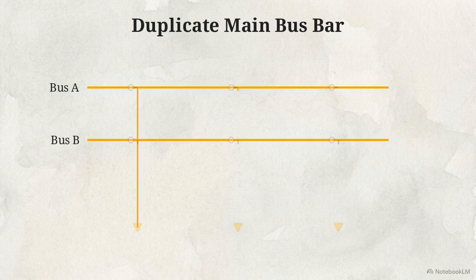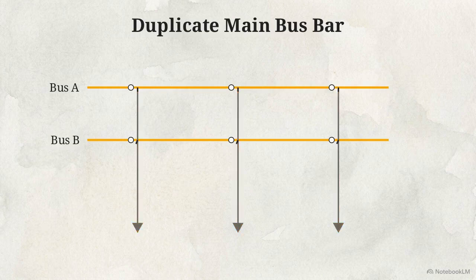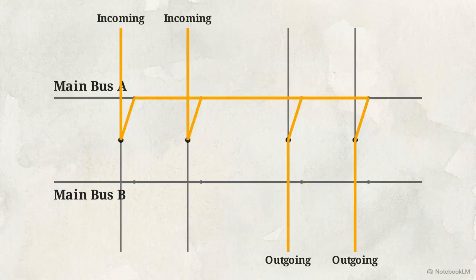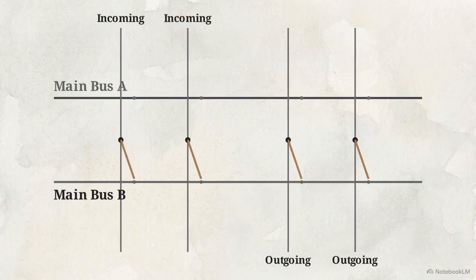This features two fully capable parallel main buses. Feeders can be physically switched to connect to either bus using isolator switches. This provides massive operational flexibility. A utility can completely de-energize one bus for maintenance without dropping a single megawatt of active load. During a severe fault on bus A, the system responds rapidly. All incoming and outgoing loads can be routed down through bus B, maintaining uninterrupted power flow across the entire node.